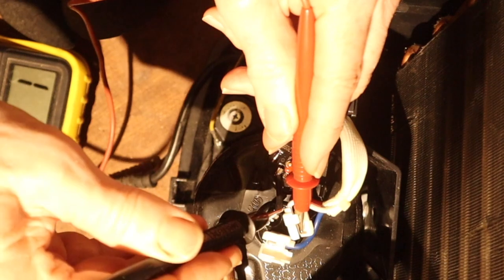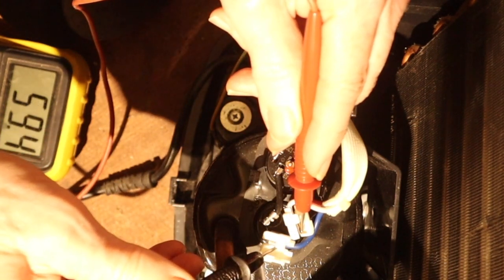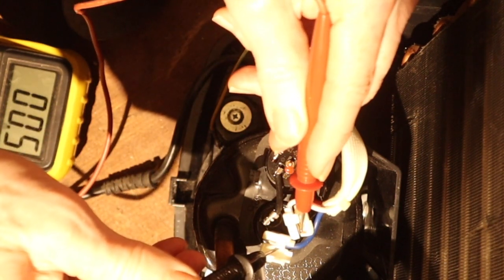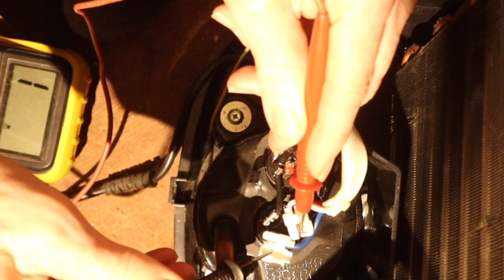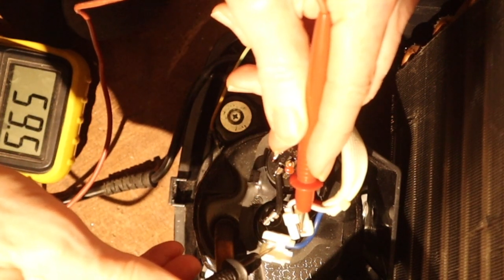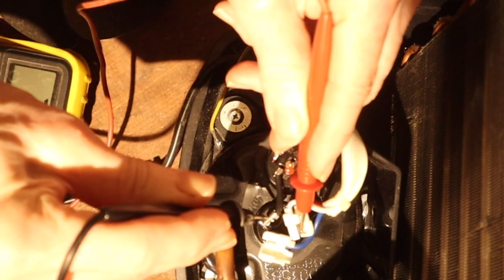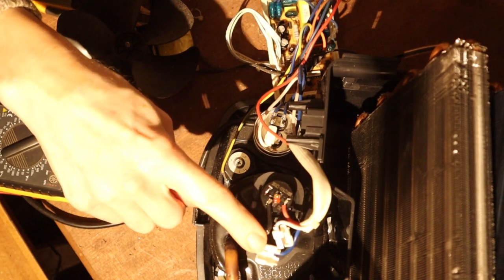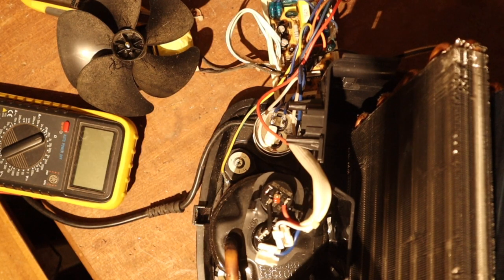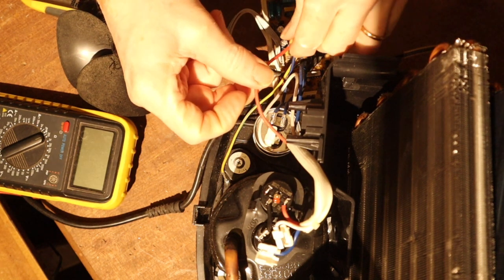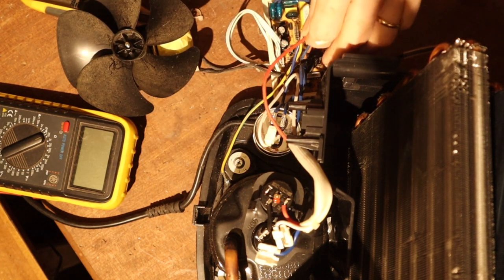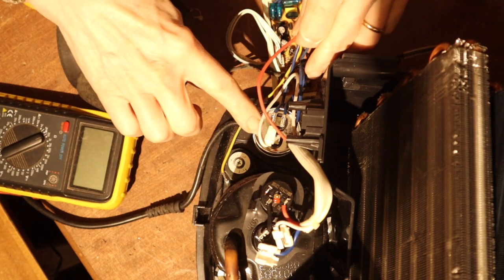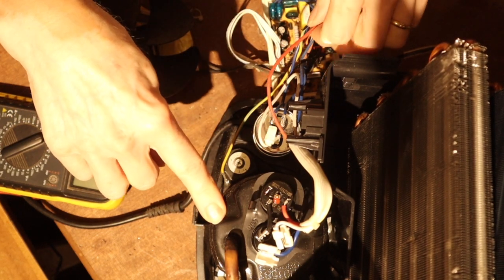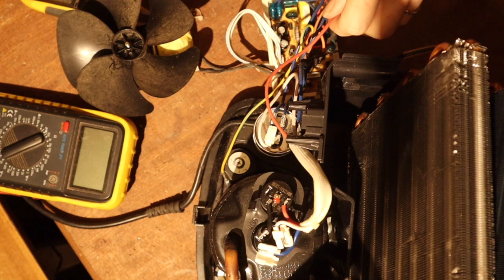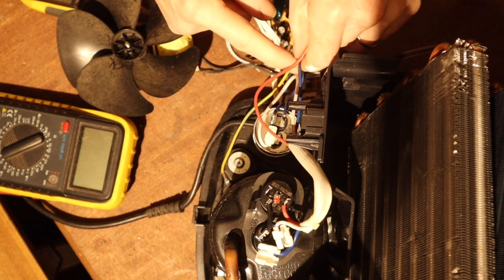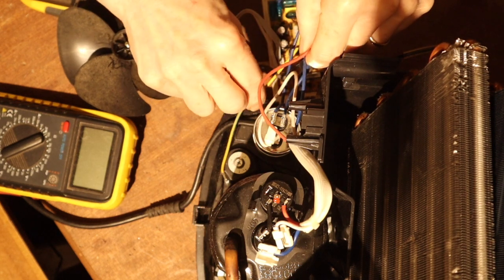So this 60 ohm, this is the capacitor, blue and white is the capacitor. That means white is the common, and this is the start winding, the blue is the start winding, and then this is the power winding. That makes sense, because here we have the live connection to this whole combination of capacitor and compressor, and here the blue is the neutral, and then we have the ground.